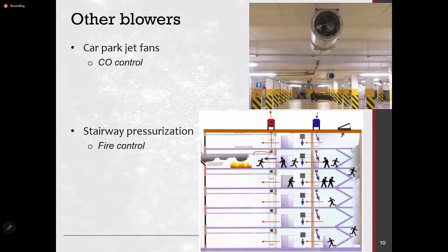So the fire will not come inside the staircase, and you can ensure that even people above can come down. So you pressurize the system and there is a pressure control. If the pressure goes beyond the limit, you can take it out, because high pressure will also be uncomfortable for the people coming down. So this is also part of the smoke control, where you have exhaust to take the smoke off from the space. Heavy ventilation can also increase the fire spread. So that's why you have to be very careful whether you're actually using this type of smoke control system.